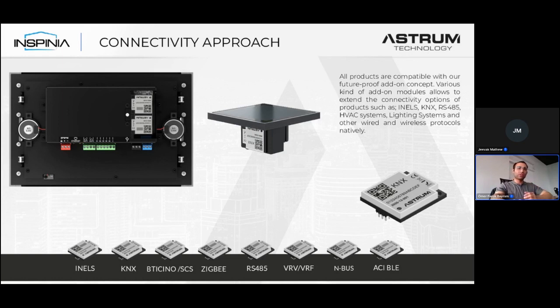We can use the other port for other protocols, or VRF solutions. For example, if we have a Daikin VRF, we can put a Daikin add-on to the second port, and we can combine this project, so we can control the VRF system through the iNELS bus, iNELS thermostatic devices, for example.